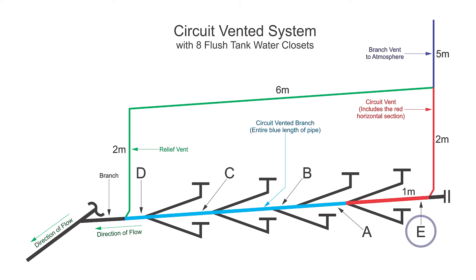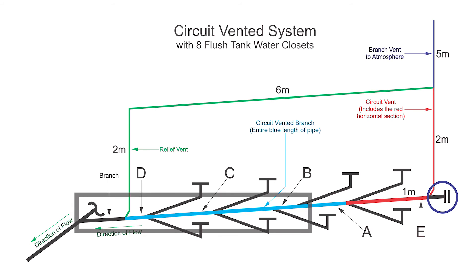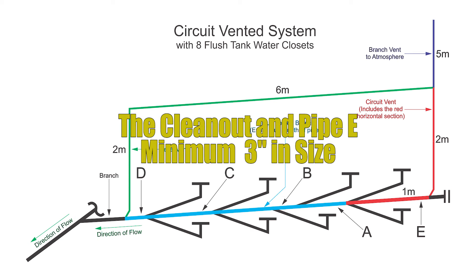Pipe E is just part of the circuit vent. However, just to the right of it is a clean-out fitting. This clean-out needs to serve the 4-inch pipe that goes from B through to the end, so that clean-out needs to be a minimum of 3 inches in size. Therefore, pipe E needs to be a minimum of 3 inches.